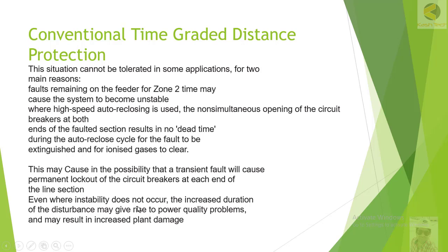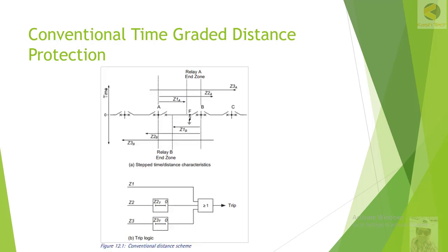Even where instability does not occur, the increased duration of the disturbance may give rise to power quality problems and result in increased plant damage. The fault feeding will obviously increase instability and result in poor power quality — there may be voltage dips and frequency dips. For example, if the fault is at F, one breaker will trip immediately while the other breaker trips after a time delay of 300 milliseconds.